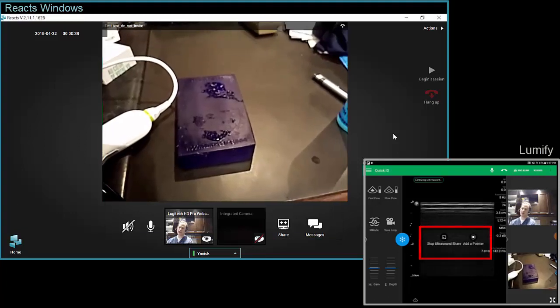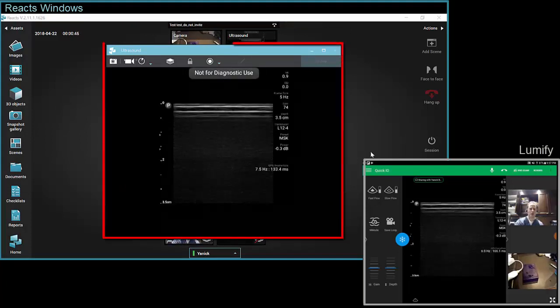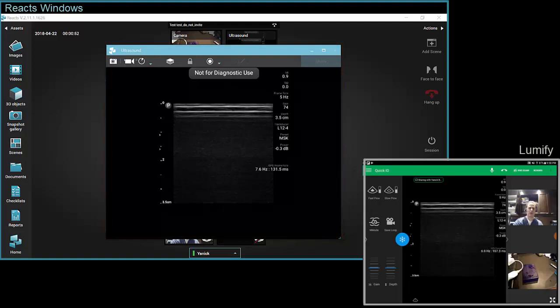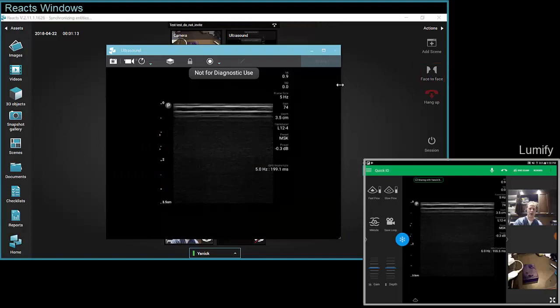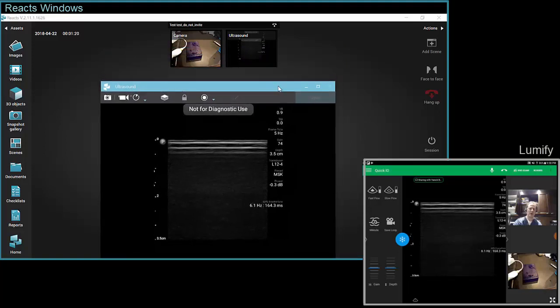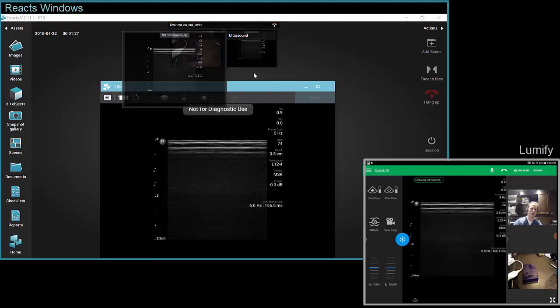In face-to-face mode you see the webcam nice and big. As soon as the Lumify user hits share ultrasound, on the Windows side you automatically go into what we call session mode, and in the middle you will see the ultrasound video stream appear automatically. If you would like to go back to face-to-face, the Windows user can just hit face-to-face to see the camera of the Lumify device again. On the Lumify device nothing changes — they keep the same interface — so the Windows user can switch between modes without interfering with what the Lumify user sees.